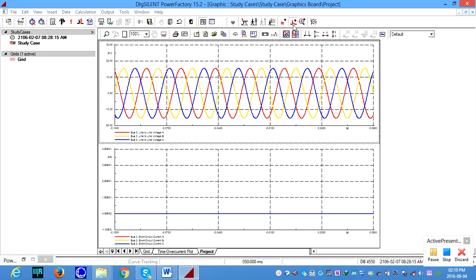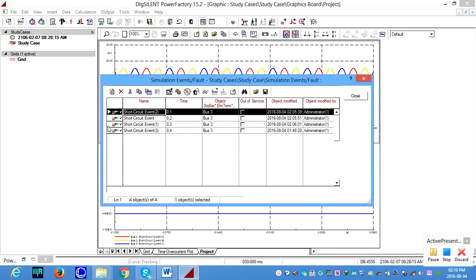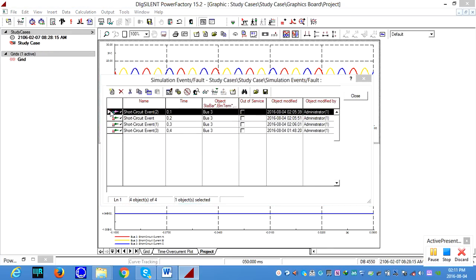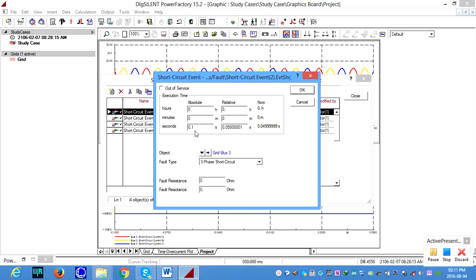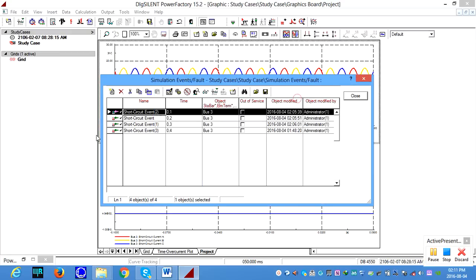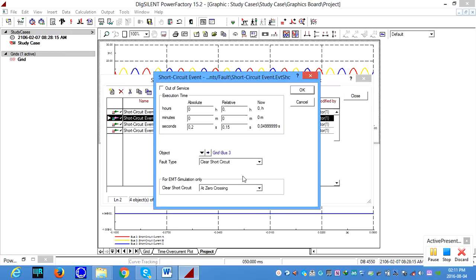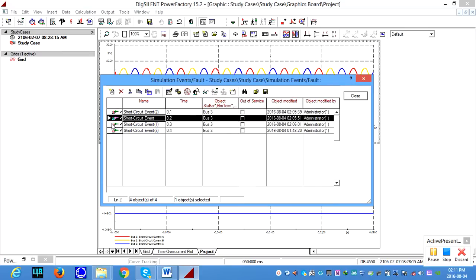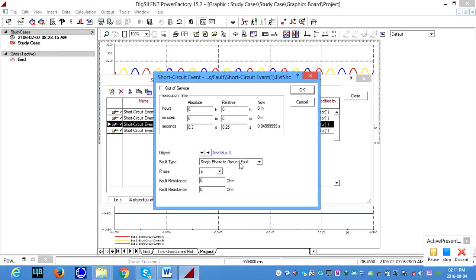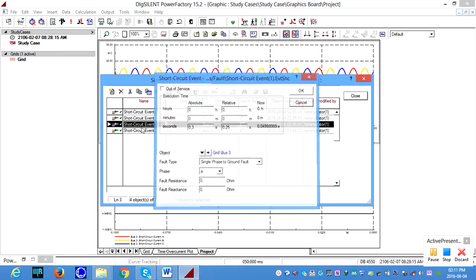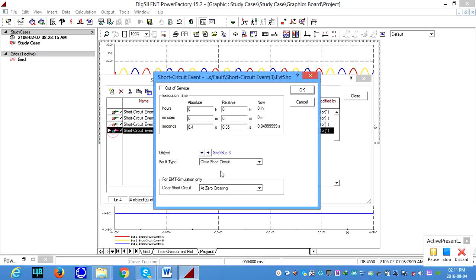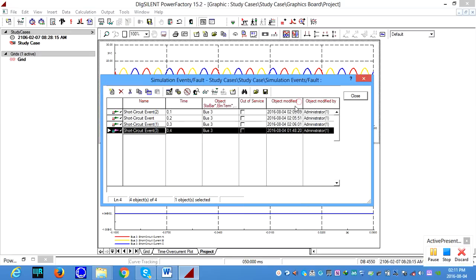Now we also want to validate. You see, this is a short circuit. This is a three-phase short circuit. It is executed at 0.1 seconds, and there is a clearing of the short circuit at 0.2 seconds. And this is the event that we defined: a single-phase to ground fault at 0.3 seconds, which is cleared at 0.4 seconds.